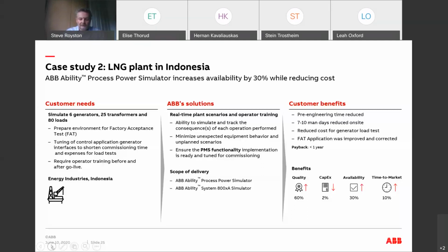So that was the purpose, to do the FAT and find either faults in the control system or the application, and tune that application to meet what we call the adequate response to the different disturbances they introduced here. Another thing was the tuning of the generator interfaces. Our power management system sends discrete control signals to the generator. So by tuning the generator and parameters in the model, we are able to have a very realistic dynamic response of that generator.